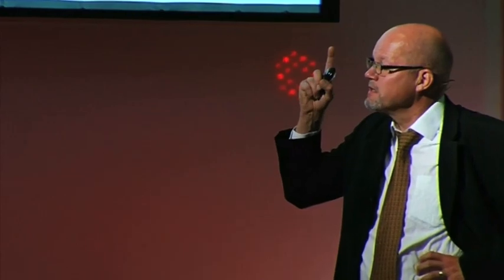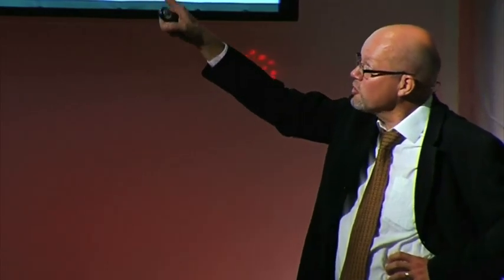The concept is very simple. You can see from the photograph that it is a modular structure. It is actually about 1 megawatt in power. The input voltage to this transformer is 15 kilovolts, 16.7 hertz, single phase, and the output is 1500 volts DC, for what is actually a DC drive, I think, in this locomotive. It is quite old, but it could also be an AC drive.